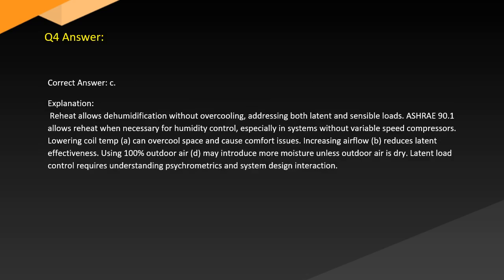Answer. Correct answer: C. Explanation. Reheat allows dehumidification without overcooling, addressing both latent and sensible loads. ASHRAE 90.1 allows reheat when necessary for humidity control, especially in systems without variable speed compressors.